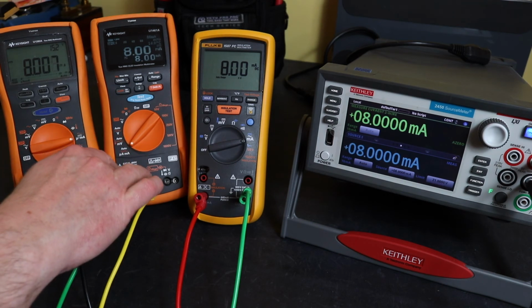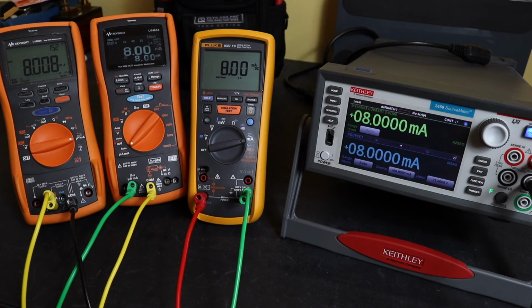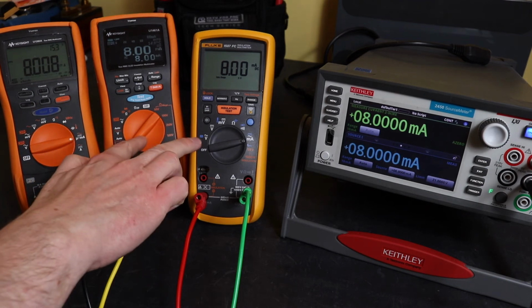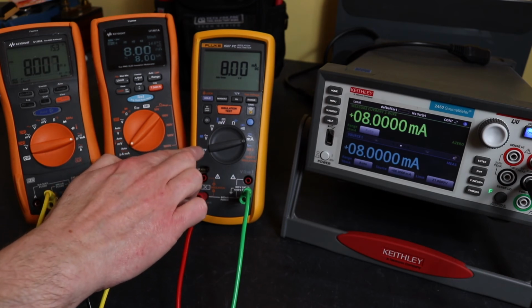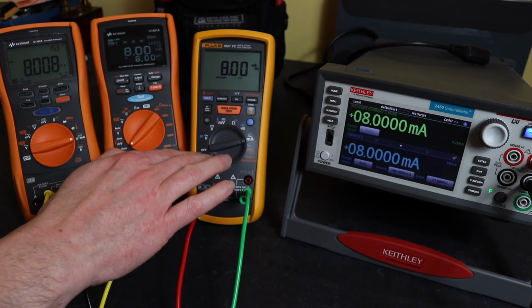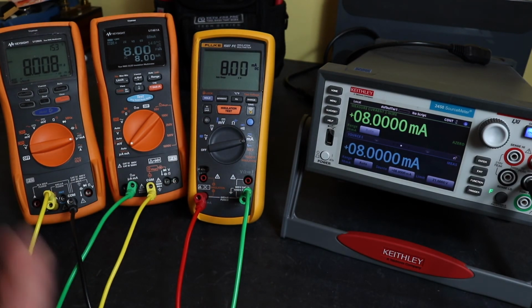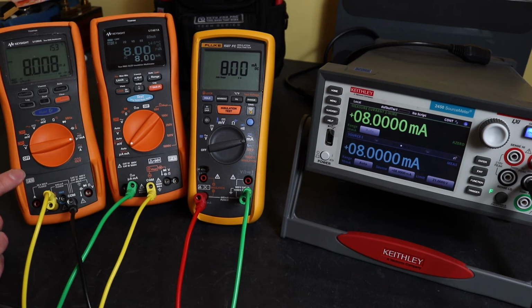The Keysight U1461A here, that is also 0.2% accuracy and also has 10 microamp resolution, exactly the same as the 1587 FC. So I don't gain anything by moving to this instrument in comparison with what I can do with the 1587 FC there. But as you can see, that also reads 8 milliamps as well. If I want to improve the accuracy, then I have to have something like the Keysight U1282A here. That is 0.05% accuracy. So that can do fairly legitimate readings, certainly on a 0.5% class transducer, but also on a 0.2% class transducer on 4 times better resolution. So I've just crept past my 3 times preference for measuring accuracy.